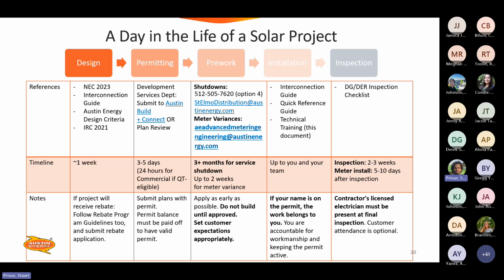Yeah, it's about a week, or 3 to 5 days, I should say, for permitting your system. As a starting point, you'll contact the Development Services Department and submit your application to the Austin Build and Connect website. You'll need to submit plans with your permit, and you have to pay off your balance before that permit goes active. And for shutdowns, that's the number right there, or they prefer email, so you can email St. Elmo Distribution at austinenergy.com. And if you'd like a meter variance, if you can't group your meters, that's going to be the email address there, AE Advanced Metering Engineering at austinenergy.com. Right now, it's about 3 months for a service shutdown, and it could take up to 2 weeks to get an approved meter variance or a response on a meter variance request. Apply as early as possible, and don't build until you've got your approval documents from us.